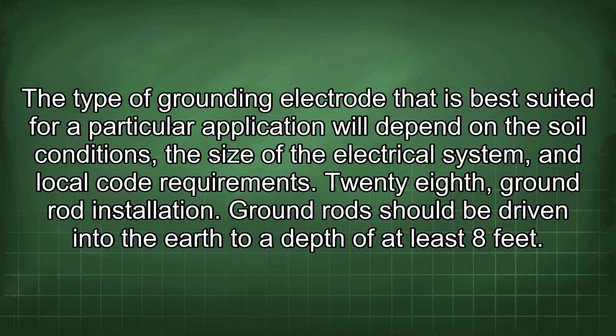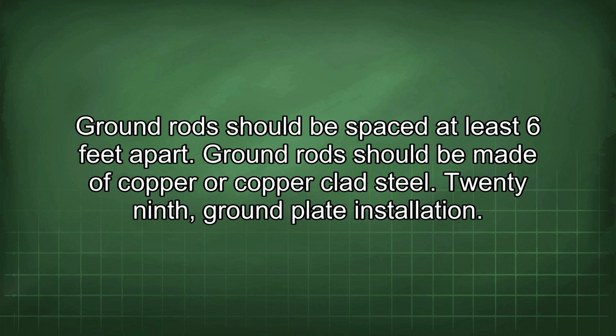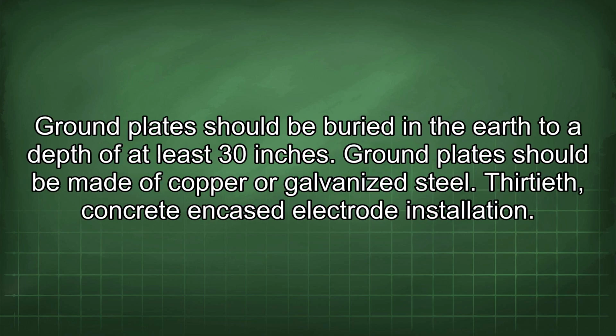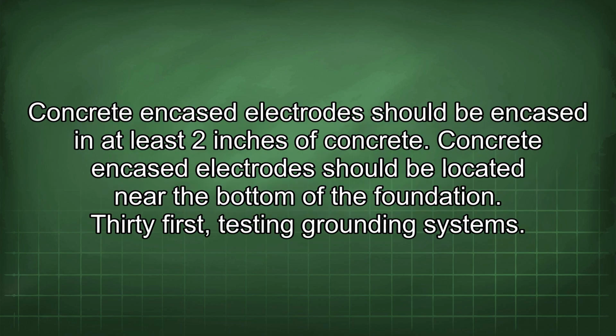28th, ground rod installation. Ground rods should be driven into the earth to a depth of at least 8 feet. Ground rods should be spaced at least 6 feet apart. Ground rods should be made of copper or copper-clad steel. 29th, ground plate installation. Ground plates should be buried in the earth to a depth of at least 30 inches. Ground plates should be made of copper or galvanized steel. 30th, concrete encased electrode installation. Concrete encased electrodes should be encased in at least 2 inches of concrete. Concrete encased electrodes should be located near the bottom of the foundation.